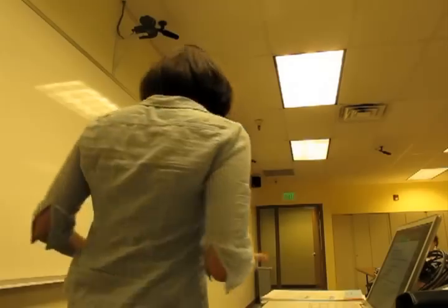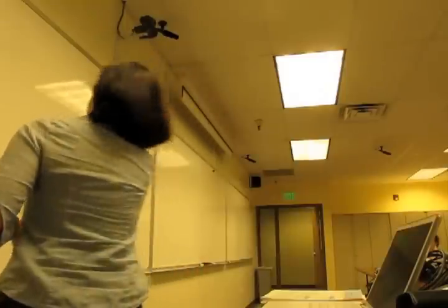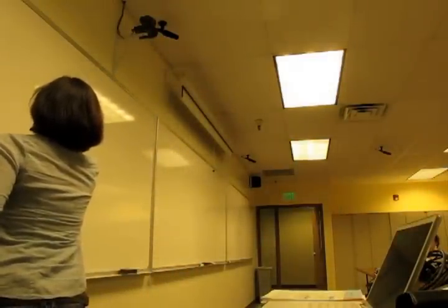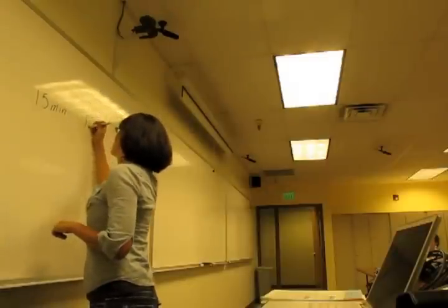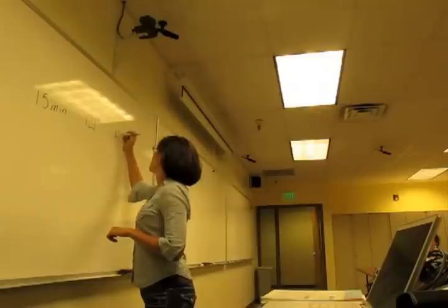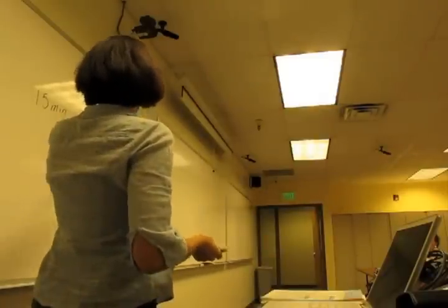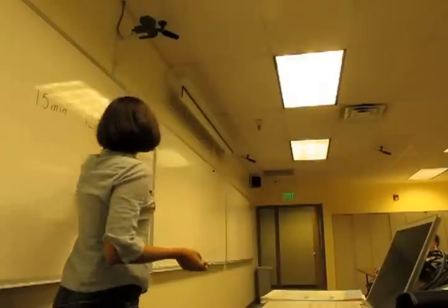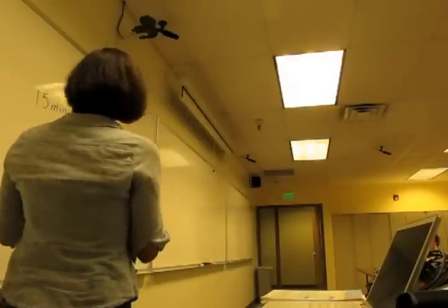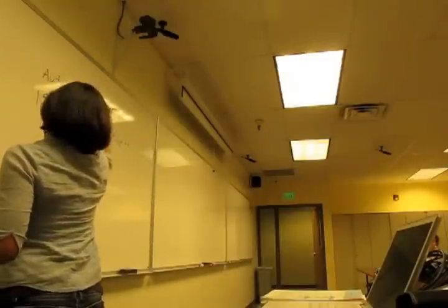So an easy way, I don't know. It's for 15 minutes, 121 degrees, and 15 pounds of pressure. It's easier for me to remember 15, 121, 15, rather than 121, 15, 15. So however you can remember it. And it's Celsius, right? Yeah.